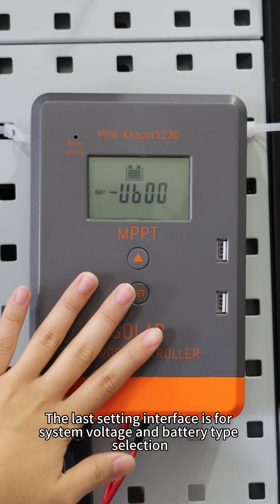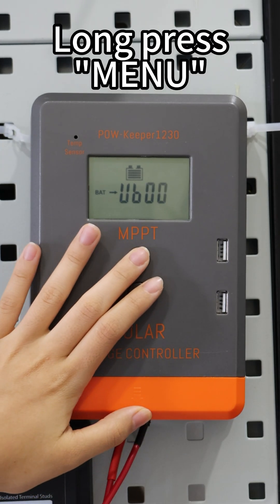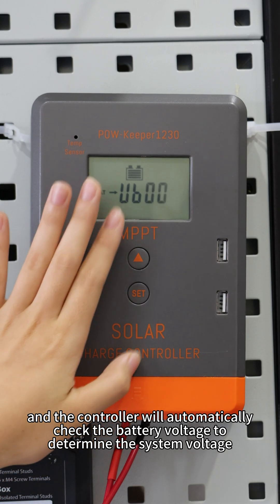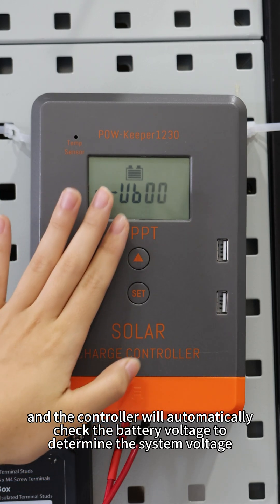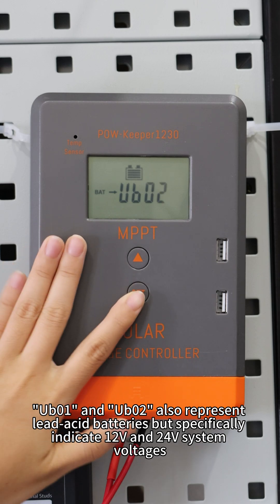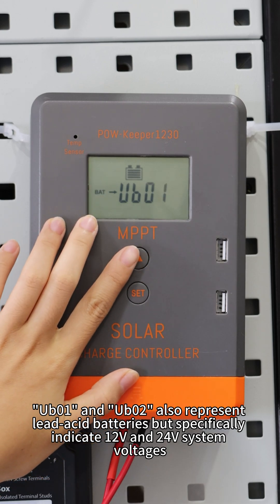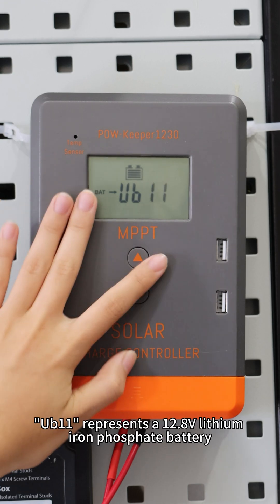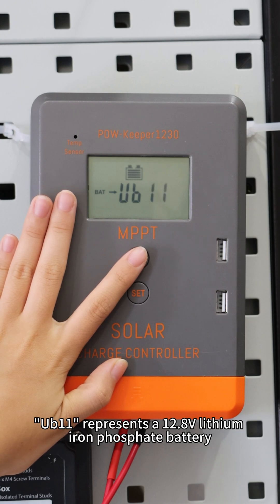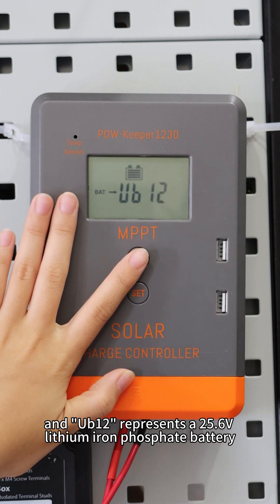The next setting interface is for system voltage and battery type selection. Ub00 represents the lead-acid battery type, and the controller will automatically track the battery voltage to determine the system voltage. Ub01 and Ub02 also represent lead-acid battery, but specifically indicate 12V and 24V system voltage. UB11 represents 12.8V lithium-iron phosphate battery, and UB12 represents 25.6V lithium-iron phosphate battery.